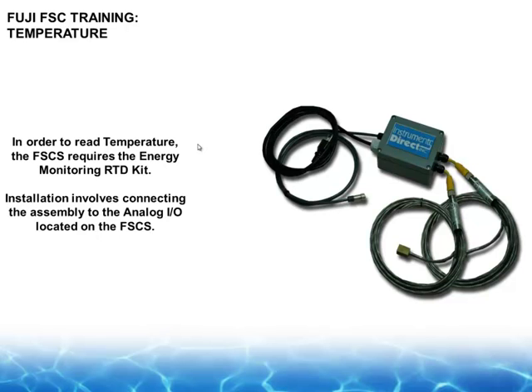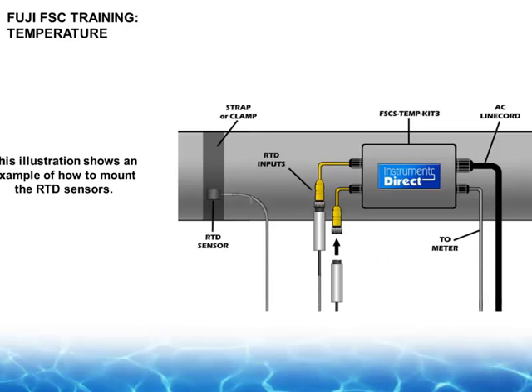And so the kit, that's an optional kit that you can add to it. You can buy it, you can rent it. It basically has a power supply and a line cord and 2 strap-on platinum RTD sensors. And the way, again, it works is you take the sensor, we give you a tube of some thermal compound like zinc oxide, real gooey sticky stuff, and it transfers the temperature from the metal pipe wall to the sensor. We strap this on the pipe there. So you can do this as a short-term test. Most BTU flow studies last a week or a month and so on. You have the ability to do that, hence why the line cord's not a big deal. No one's going to do BTU studies for 10 minutes. You're not going to have enough information there.